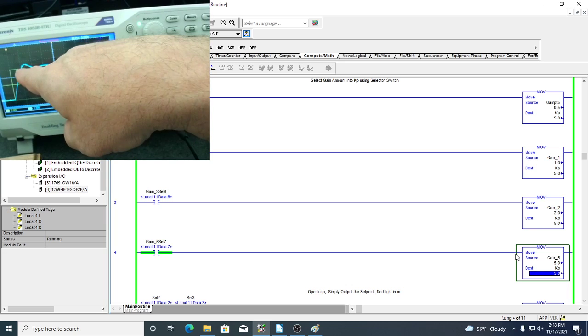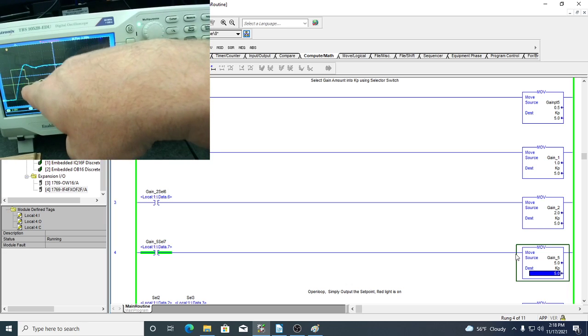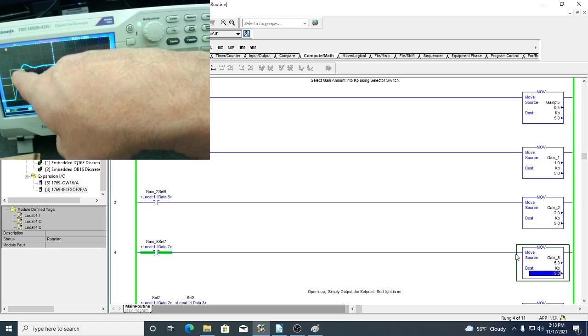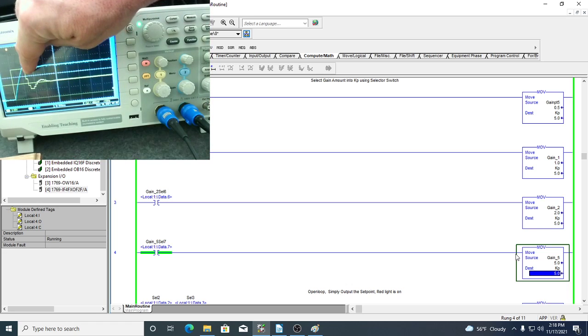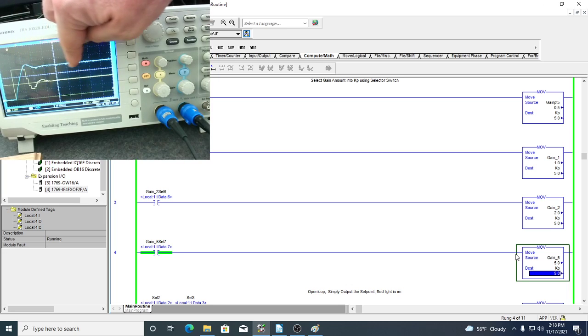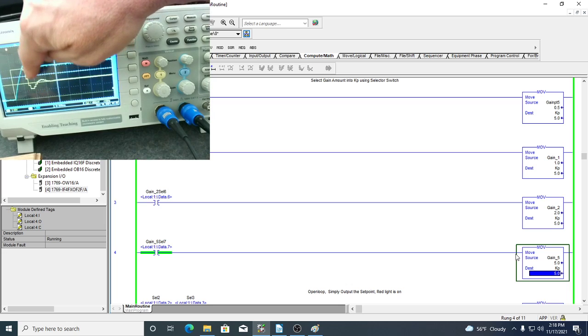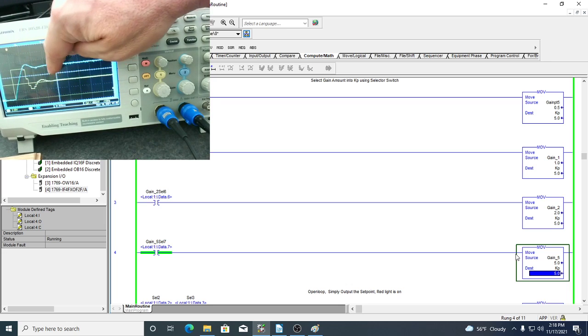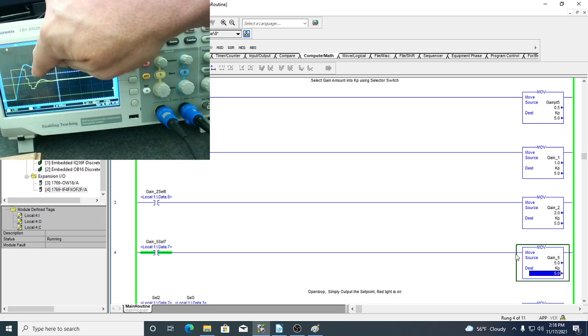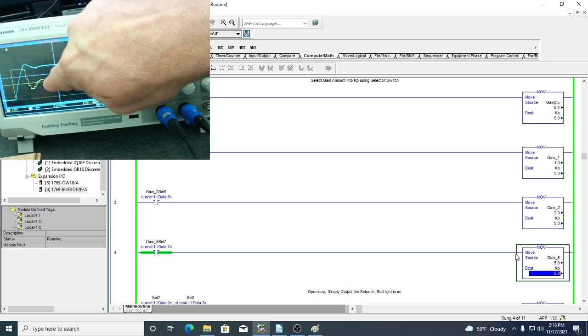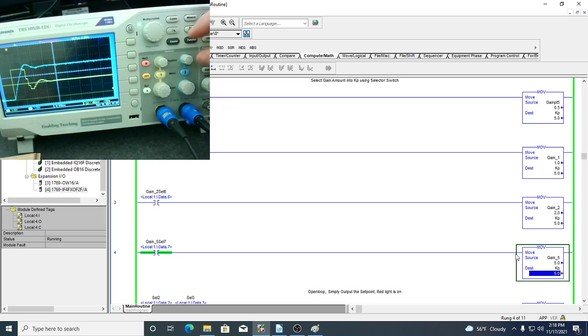Okay, and it's staying there for a while, and then once it sees that, you see right there, once the output gets above that final value, then it ends up dropping back down and trying to push the system back down, and then it's like, whoops, I pushed it too low and I need to push it back up. So you can see that's why it's bouncing around.